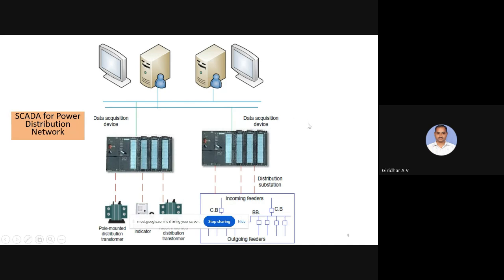So this is a typical SCADA for a power distribution network. Incoming feeders from the devices, from the CBs, all the data will be collected and monitored at the master stations. All these parameters will be taken as data, and particular servers will be there where that data will be stored and processed for monitoring, control, and protection.